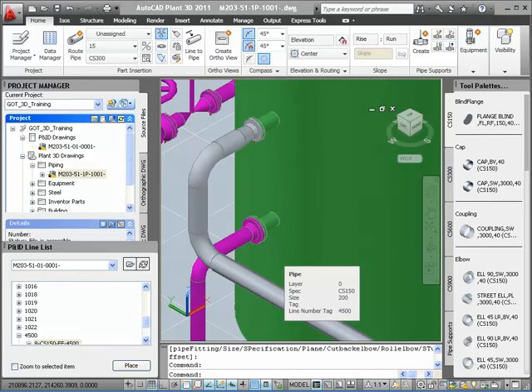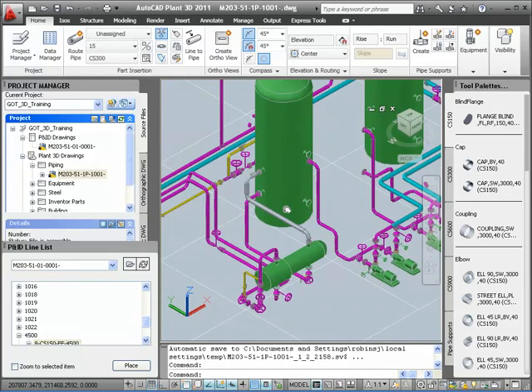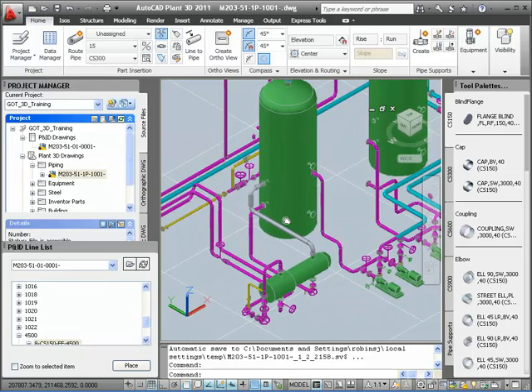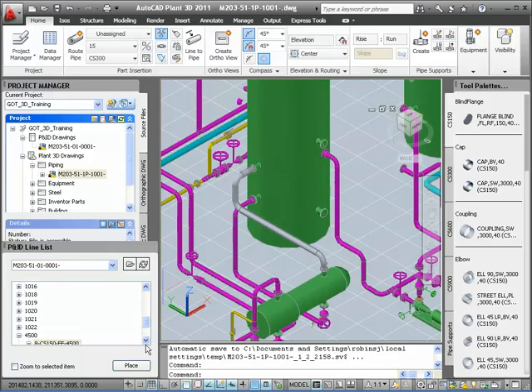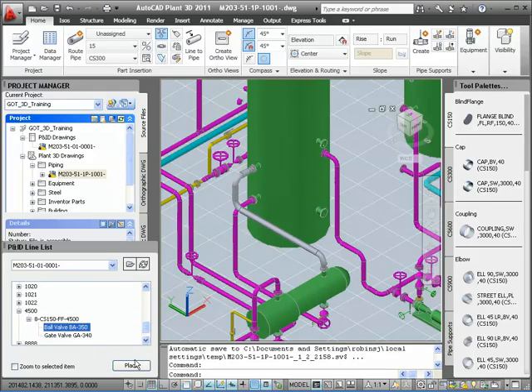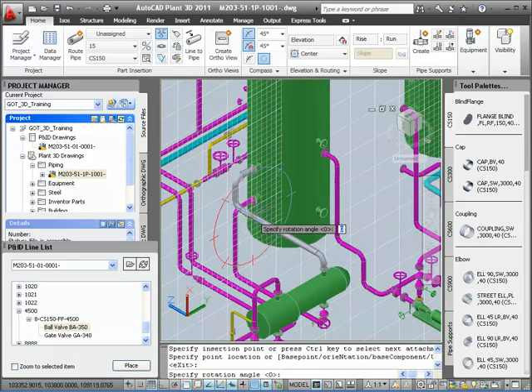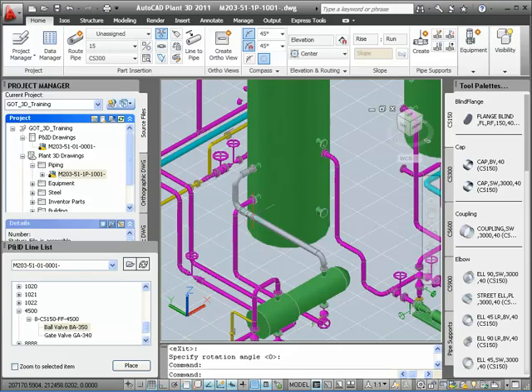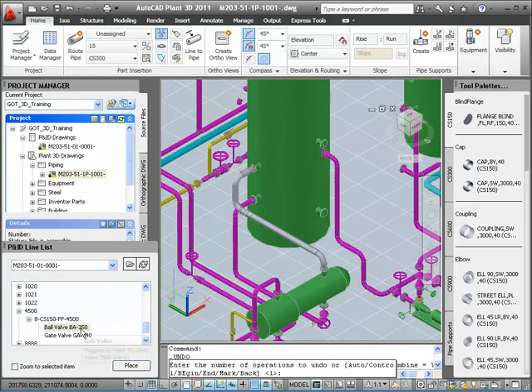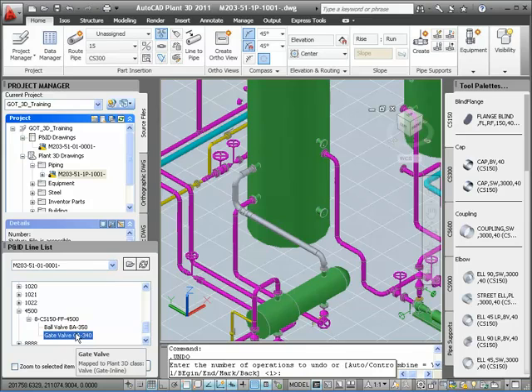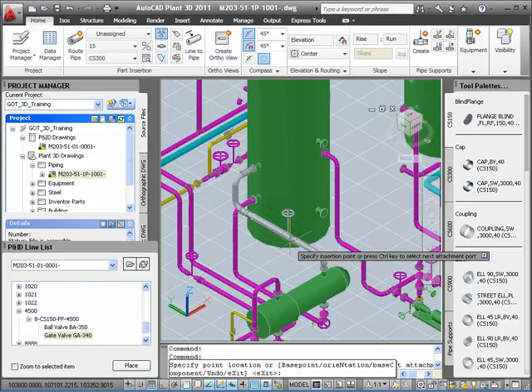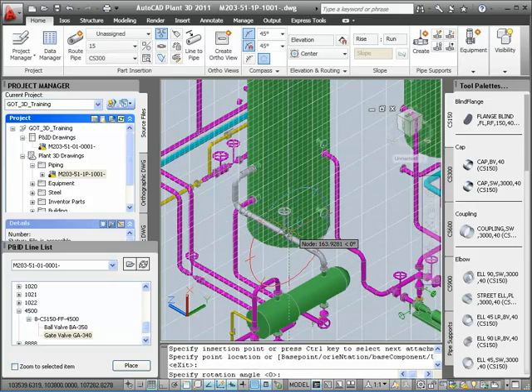If I look at the tooltip of this placed line, I'll see that I get the P&ID information — namely the spec and service — automatically in my 3D model. Now I'll add the valves. I'll expand the line list again, select the ball valve, and click the Place button. I'll place it in my line and give it an orientation. Next I'll repeat the process for the gate valve. I'll hover over each of these valves to show you tooltips — the information from the P&ID drawing has effortlessly appeared in my 3D model.